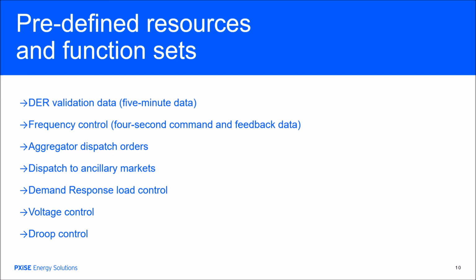It supports demand response load control, voltage control, and droop control. Through the protocol, the server can send a droop curve to the device, telling it to go on droop control with these settings for this amount of period. That period can be infinitely long or it can be 5 minutes. It's a pretty robust way to define controls for these DERs.